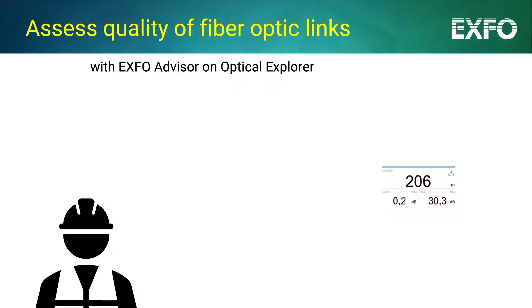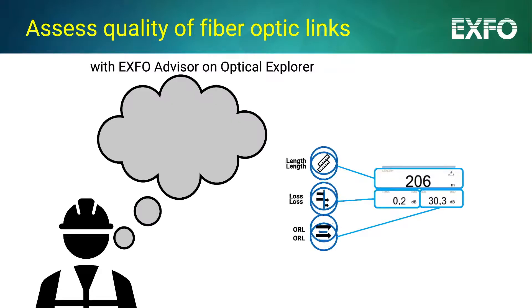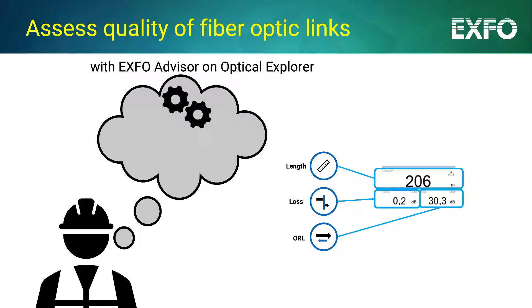To assess the quality of a link, seasoned fiber optic technicians can read the link's key performance indicators, or KPIs, which are length, loss, and optical return loss. And from these values, interpret on their own how the link compares to an ideal installation.